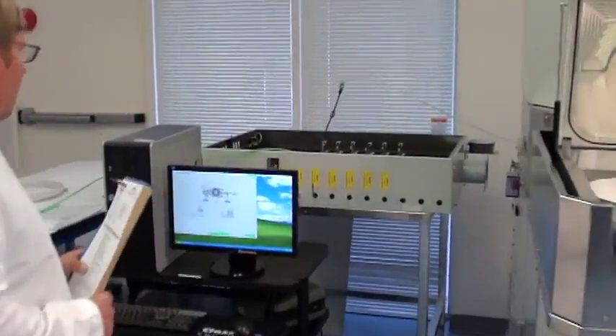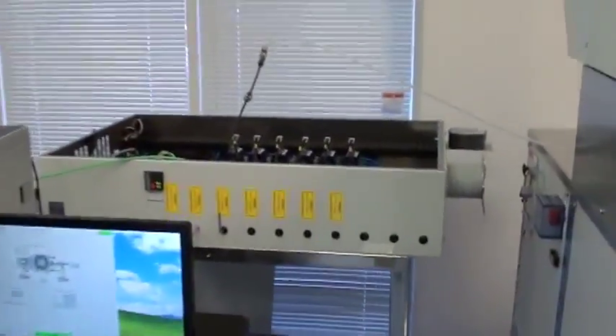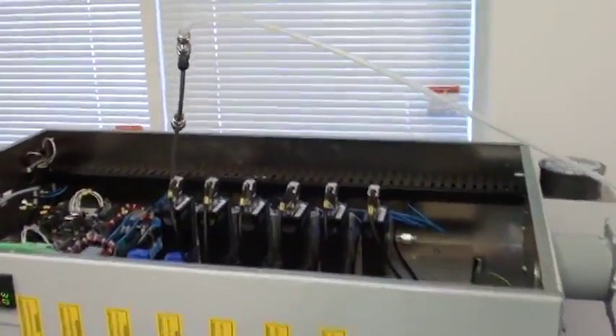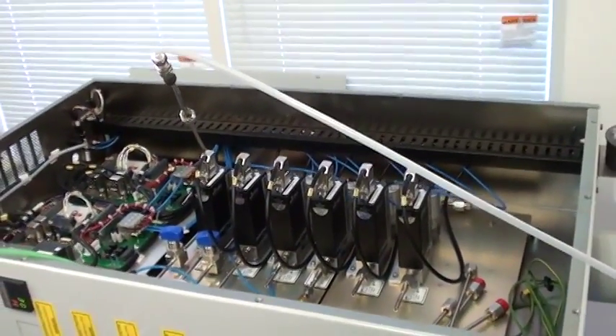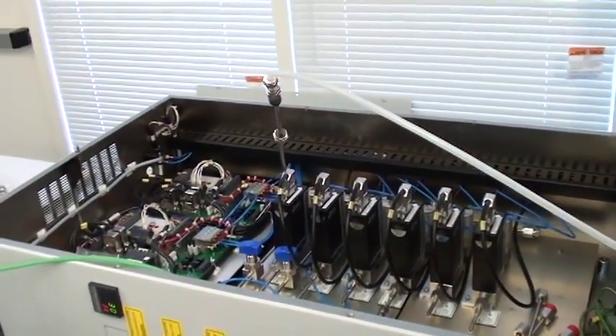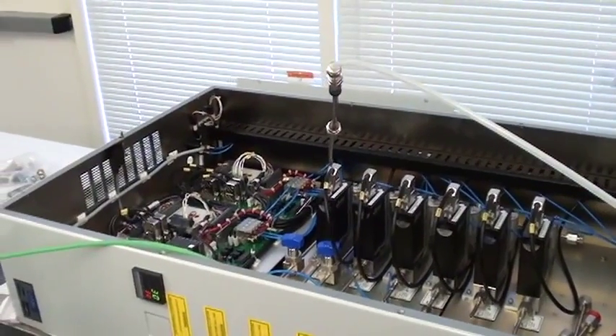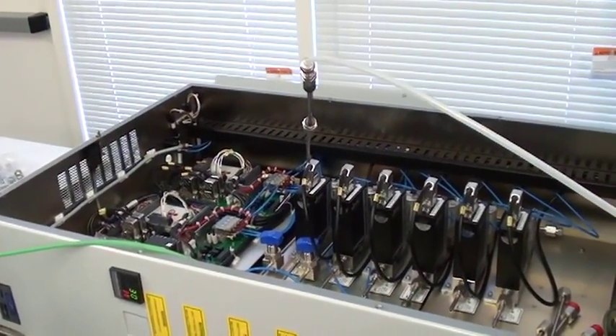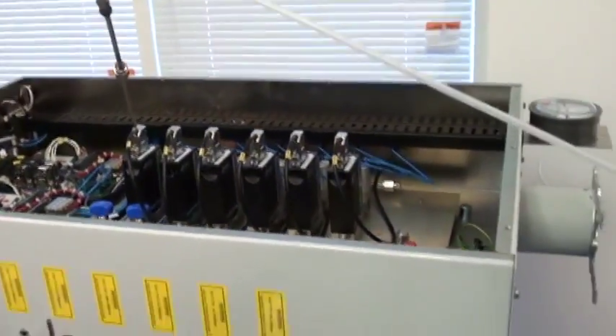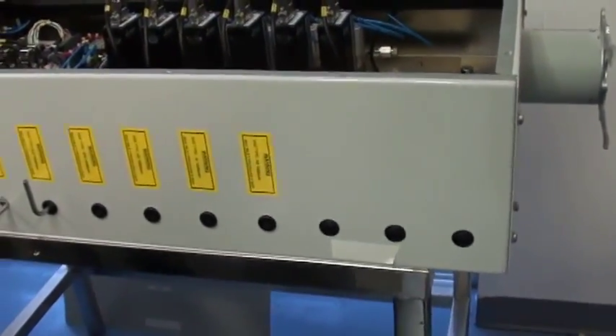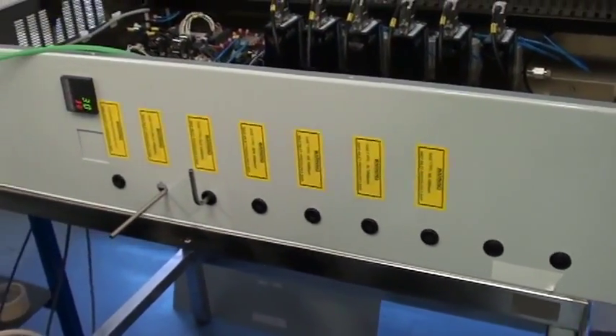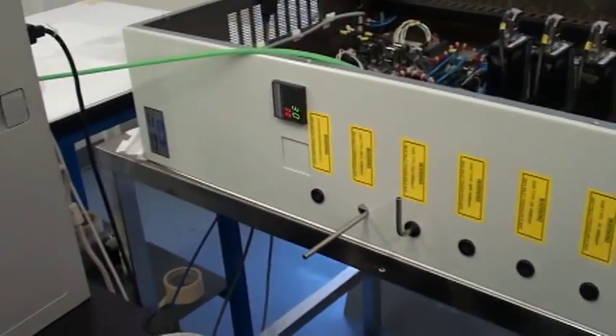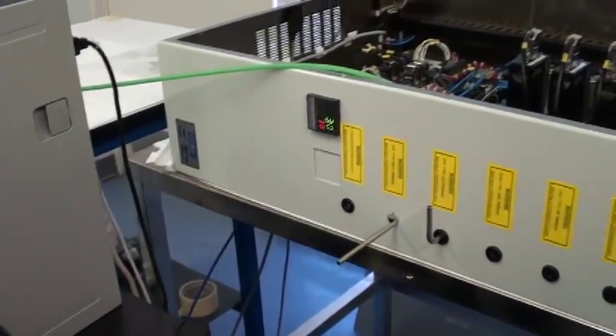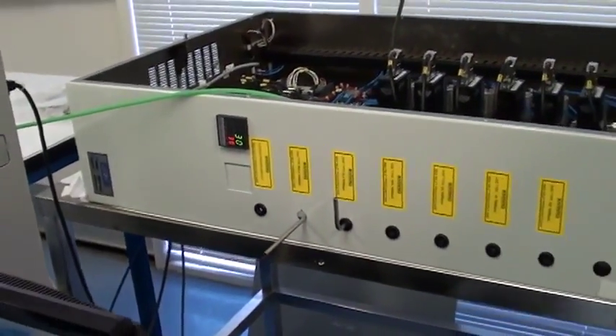We have a 6 gas pod. And in that we have BCl3, 100 SCCM, Cl2, 100 SCCM, SF6, 100 SCCM, O2, argon, and nitrogen, all three 100 SCCM. They have been sent out for clean and calibration, and we have test calibration sheets on those that stay with my rebuild folder.